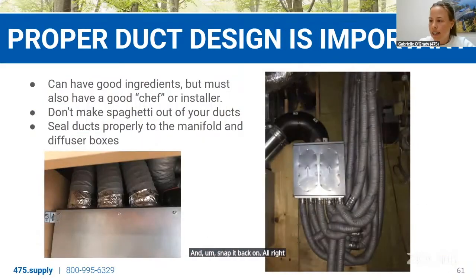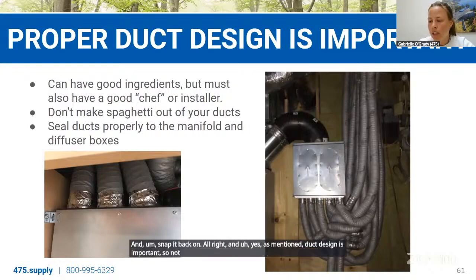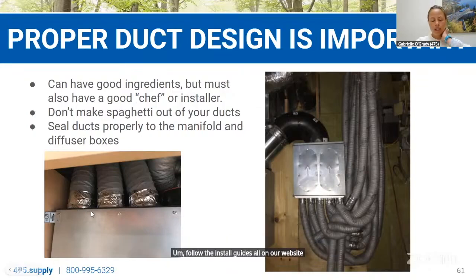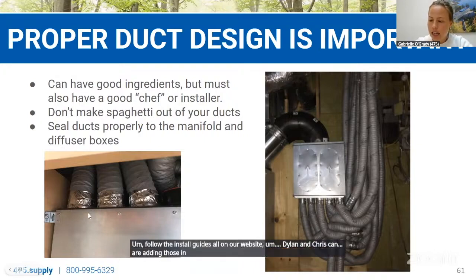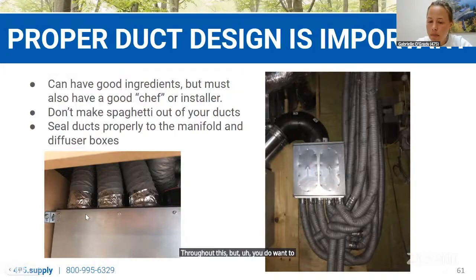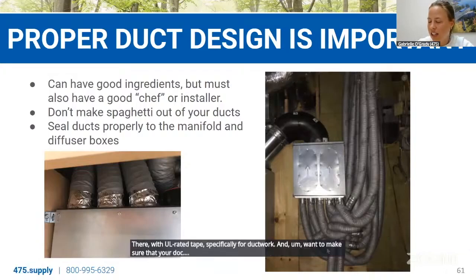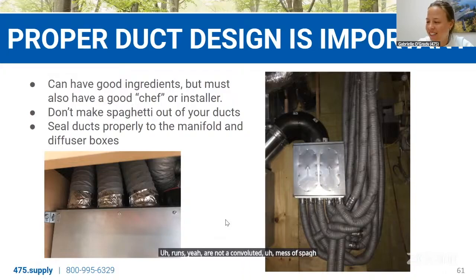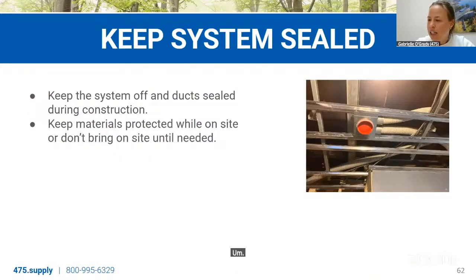All right, and yes, as mentioned, duct design is important. So not only do we want to make sure that they're pulled taut, with no tears in any of the ducting leading to leakage, we want to make sure that you follow the install guides, all on our website. Dylan and Chris are adding those in the chat throughout this. You do want to tape both ends there with UL rated tape specifically for ductwork, and want to make sure that your duct runs are not a convoluted mess of spaghetti. As mentioned, keep the system off and duct sealed during construction. Keeping it clean is important. And keep the materials protected while on site.